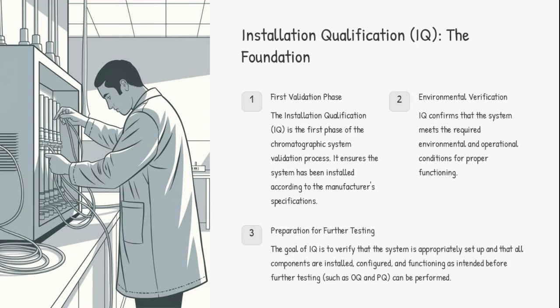Installation qualification, IQ, is the first phase of chromatographic system validation. It ensures the system has been installed according to the manufacturer's specifications and meets the required environmental and operational conditions for proper functioning. IQ verifies the system is appropriately set up and ready for further testing, such as OQ and PQ.